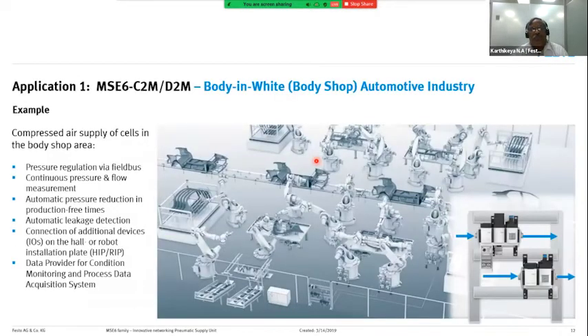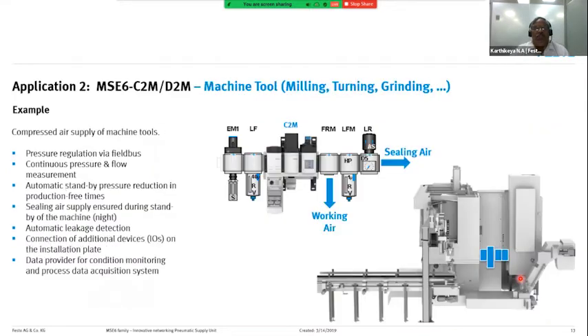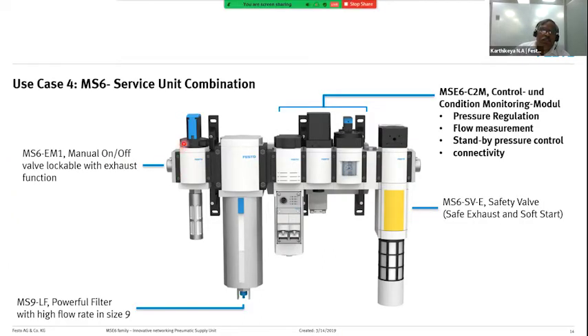Therefore, if you take industries like body in white, there are different pressure zones. Therefore, we can use a combination for a higher pressure and a lower pressure with the same communication module, and we can attain the same functionalities. Similarly, in machine tool builders, in milling, turning and grinding machines, we have to monitor the pressure, flow, and consumption. As I said, normally you have only an on-off valve and a pressure regulator. Now with this intelligence, you can add this module along in the air preparation line along with the safety module. In case of emergencies, the upstream air can be dumped immediately when you press the emergency button. Therefore, the safety valve will take care of this functionality.